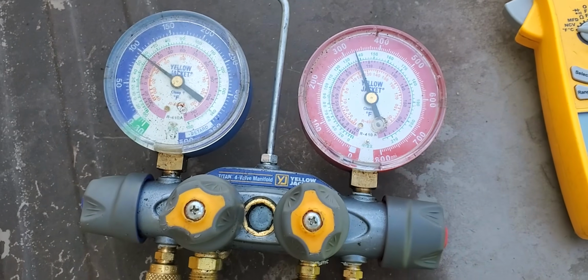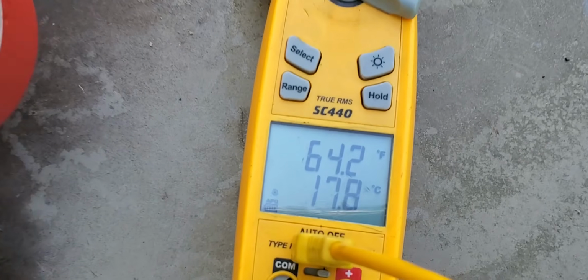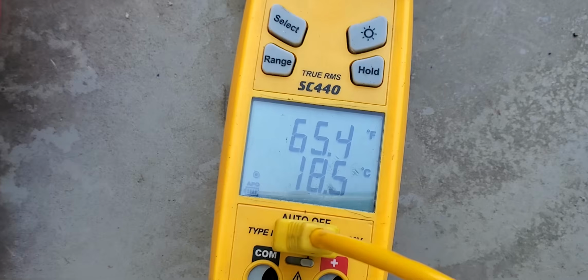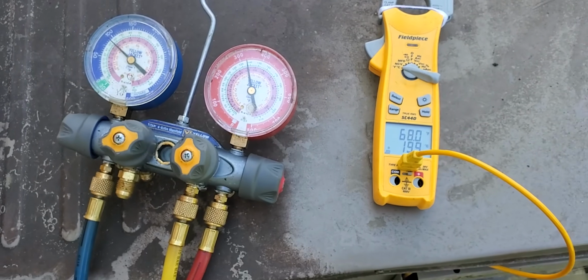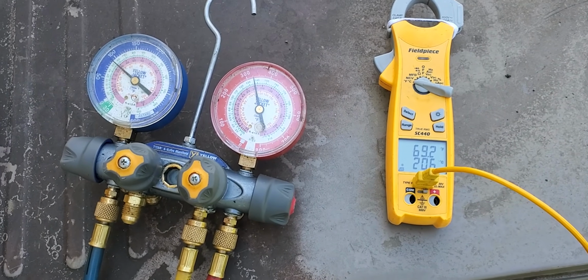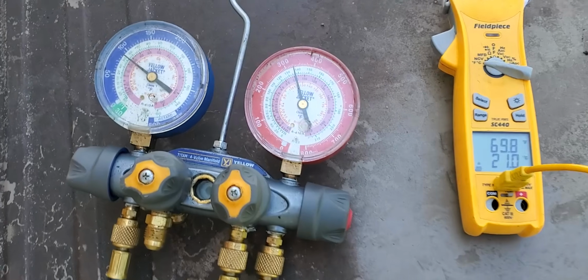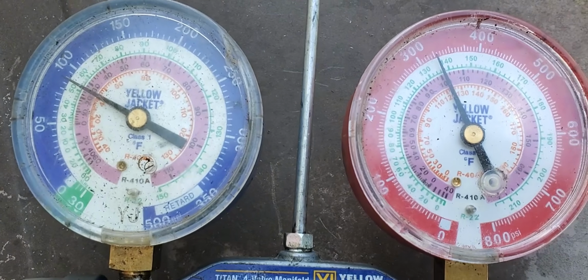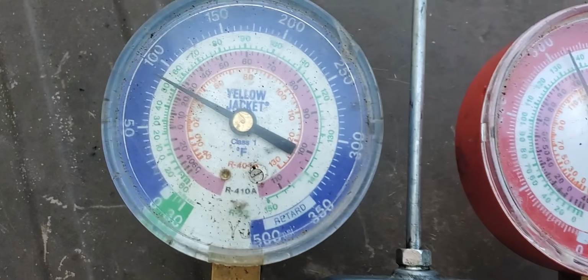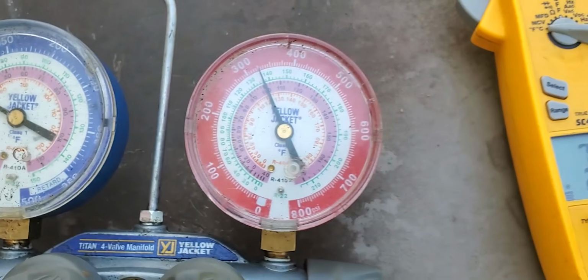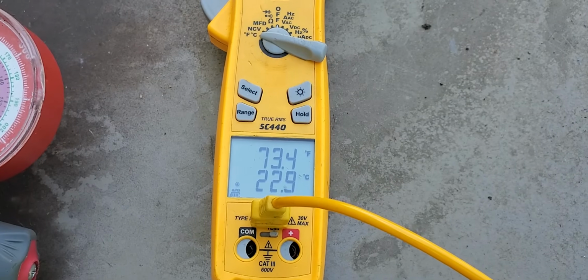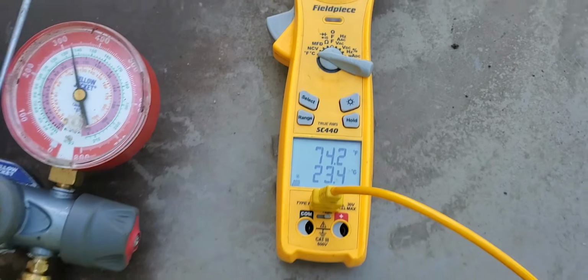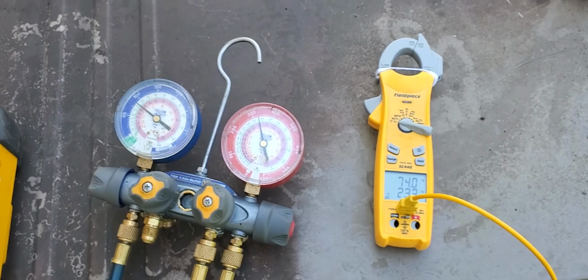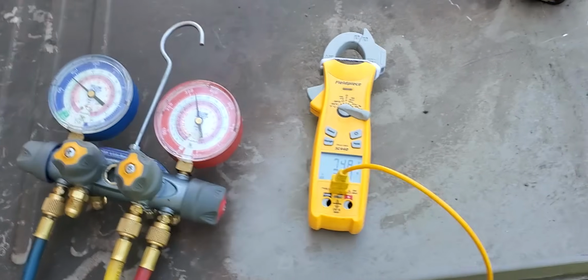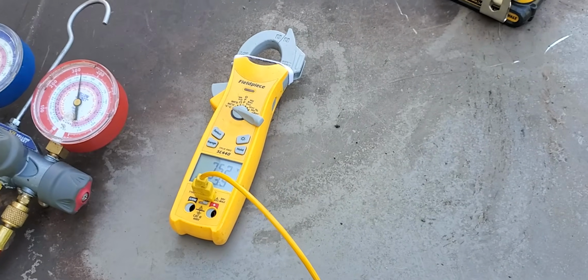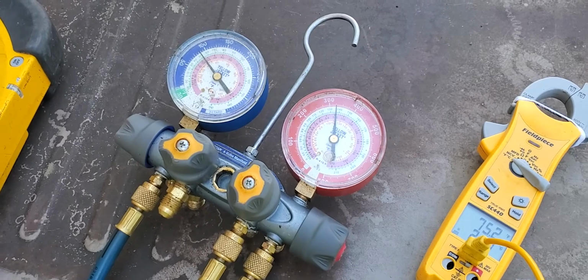Let's talk about what I'm doing here. I'm using a temperature probe and my meter to check the Fahrenheit temperature of my liquid line and my suction line. I'm going to be taking that temperature probe and connecting it to the suction line close to the compressor inlet, and then I'm going to also connect that temperature probe to my liquid line. I'm connecting to the suction line to check superheat. I'm connecting to the liquid line to check subcooling.